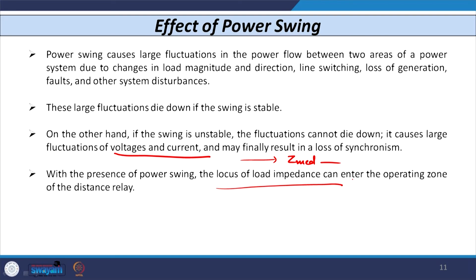But if the swing is unstable, the fluctuations may take a long time and may not die down, and they cause large fluctuations in the voltages and currents. Because of that, the impedance measured by the relay is also affected. So, because of power swing, the locus of impedance can enter the third zone of the distance relay and the distance relay may maloperate.